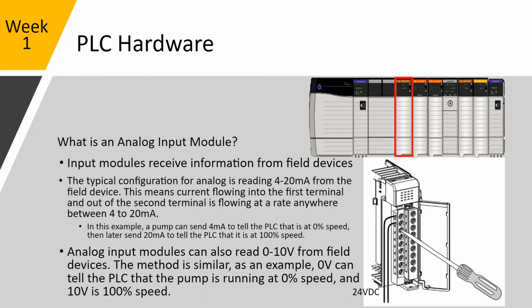So if you have a pump that's on or off, but that pump can run at different speeds, your 4 to 20 milliamp signal is going to tell how fast that pump is running. So 4 milliamps would be set to 0%, and 20 milliamps would be set to 100%. The processor will interpolate what the signal is. So at 12 milliamps, that would be 50%.